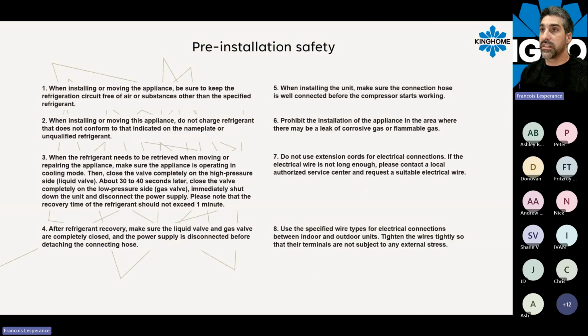So pre-installation safety: it's just good to keep in mind that just before you do a unit replacement or a new installation, make sure your system will be kept clean. So if you reuse, for example, the refrigerant line already in place, make sure you take a look at it, and check there's no blockage, no dirt inside of it, or excess amount of humidity. So you need to keep these pipes clean.